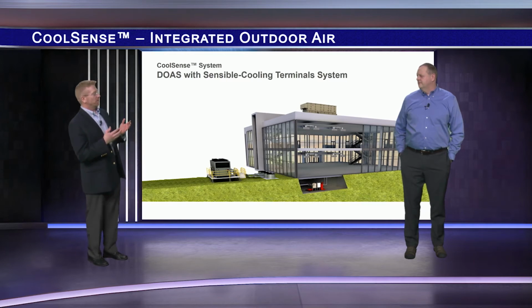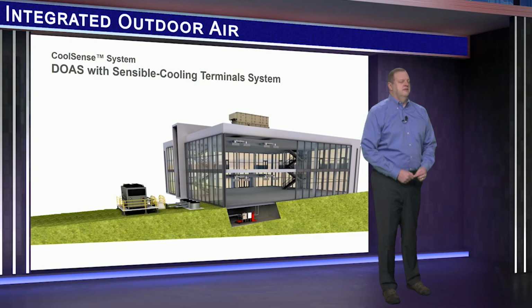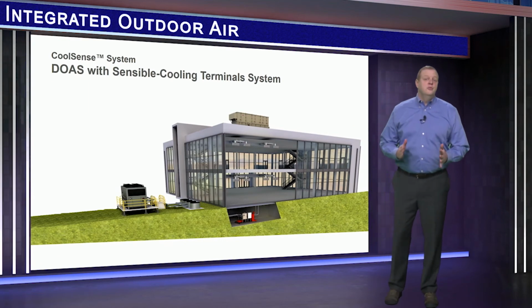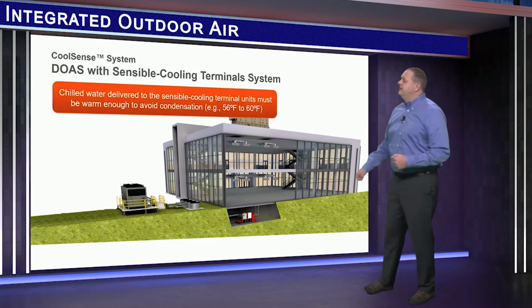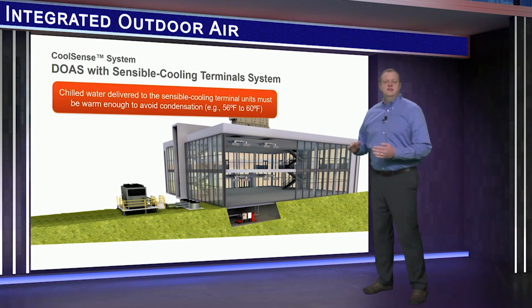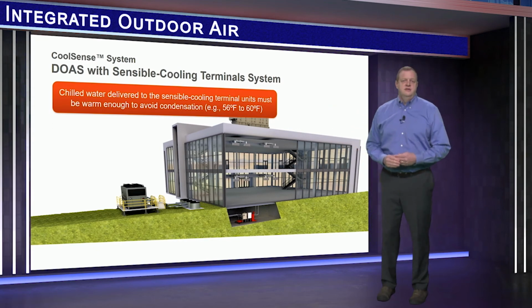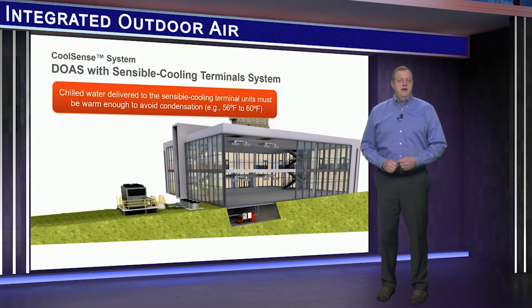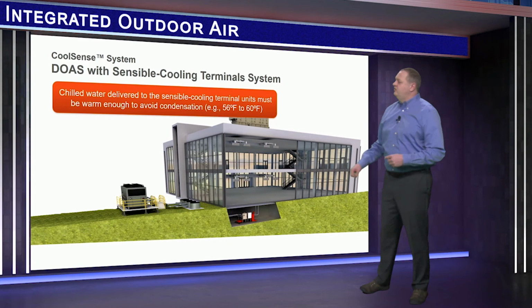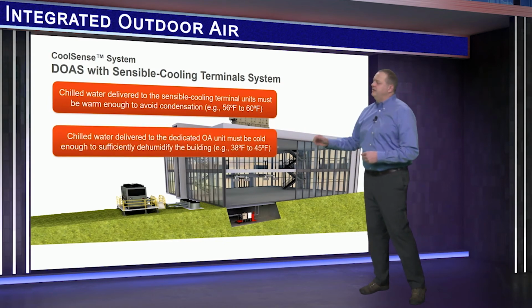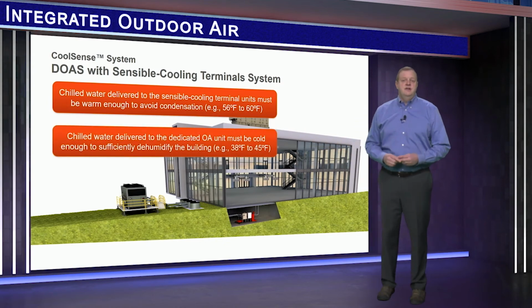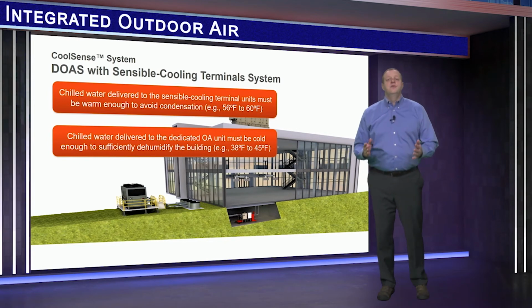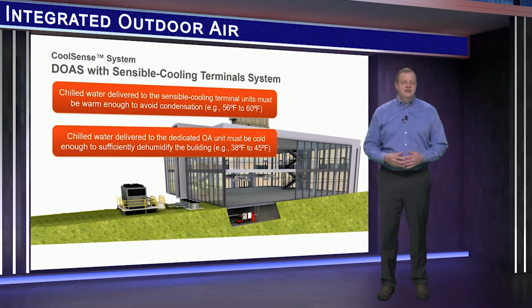John, let's start with the fundamental difference from a traditional chiller plant. As we discussed, the chilled water supplied to the sensible cooling terminals is typically between 56 and 60 degrees to avoid condensation. But in order for the dedicated outdoor air unit to dehumidify enough to keep the indoor dew point below 55, the chilled water supplied to it will likely need to be in the range of 38 to 45 degrees. Now there's a wide variety of plant configurations that can deliver these 2 different temperatures, whether a single chiller is used or multiple chillers.